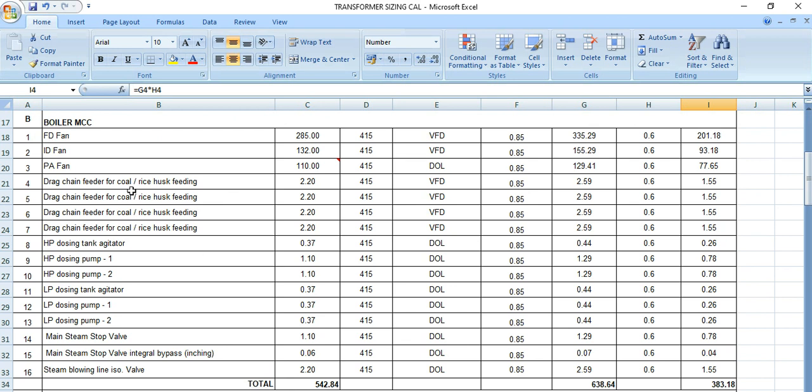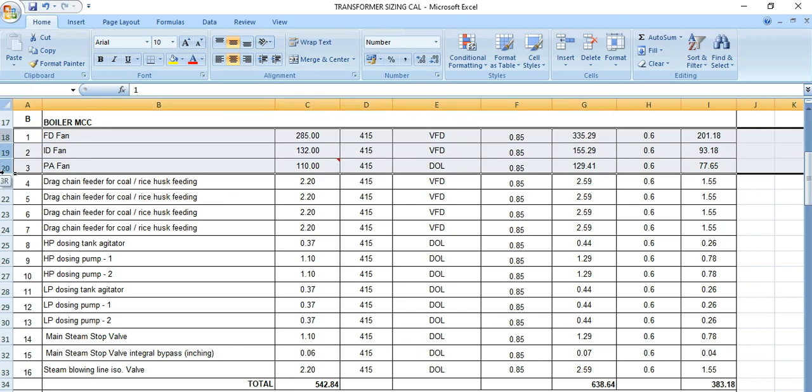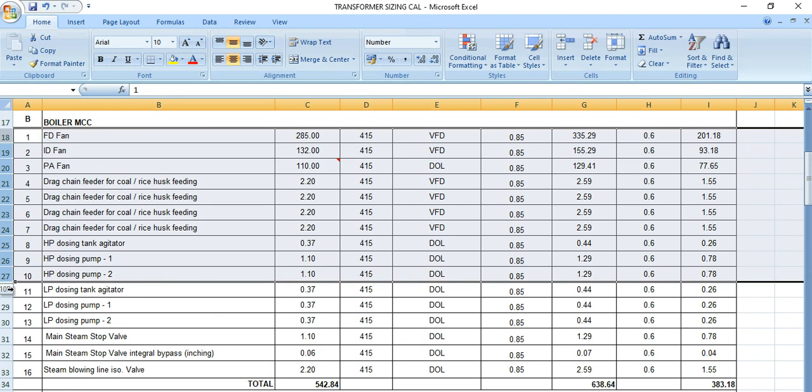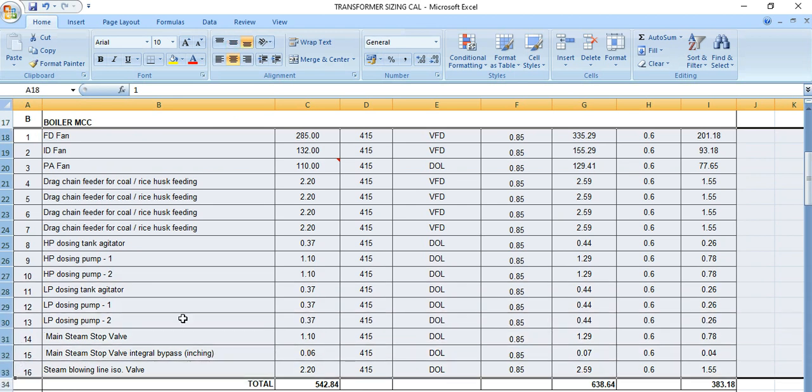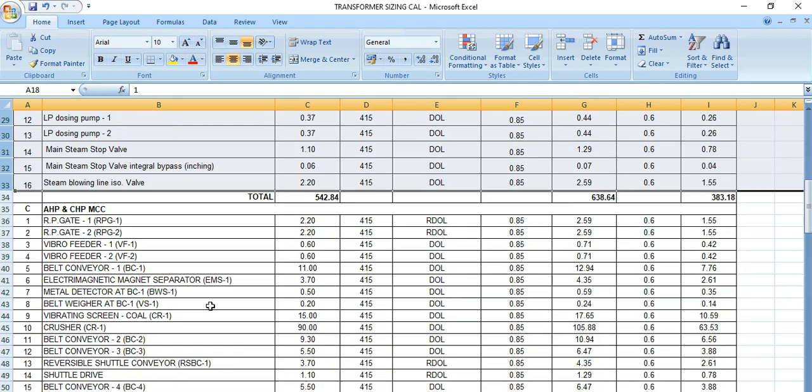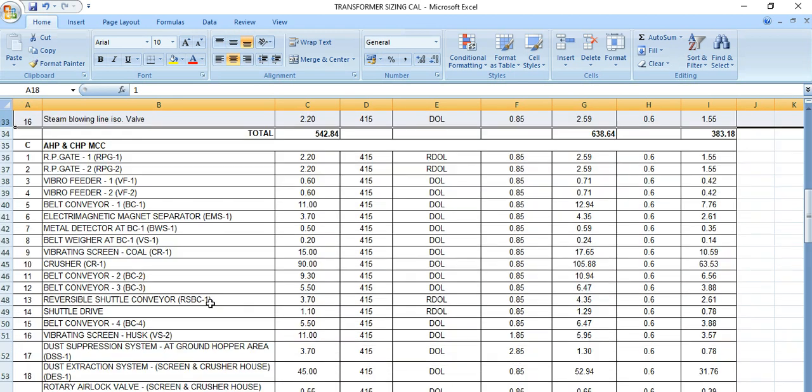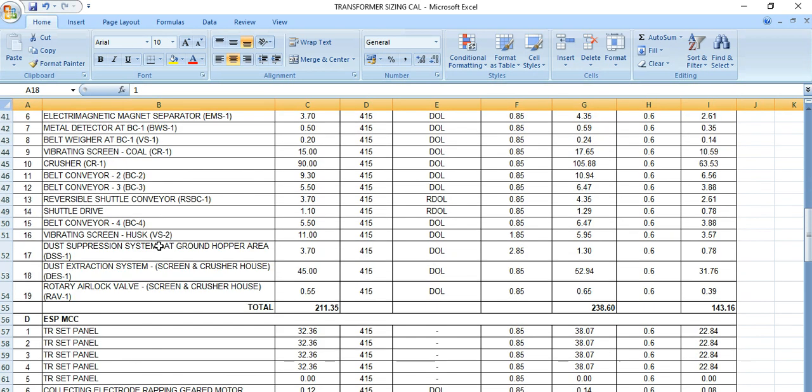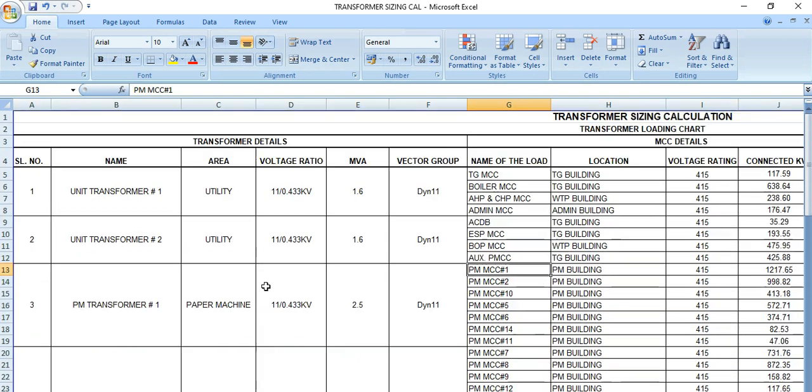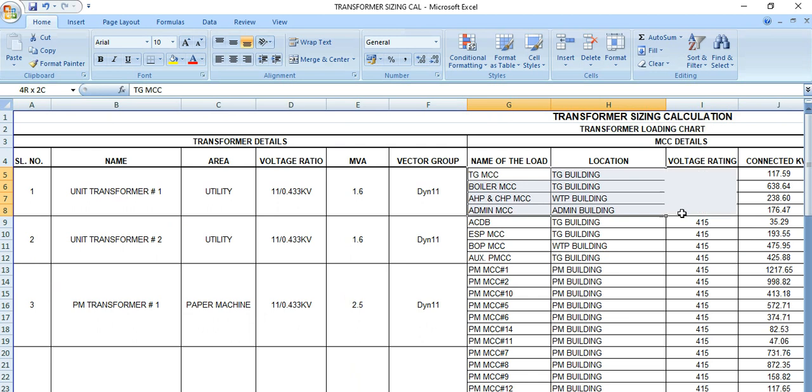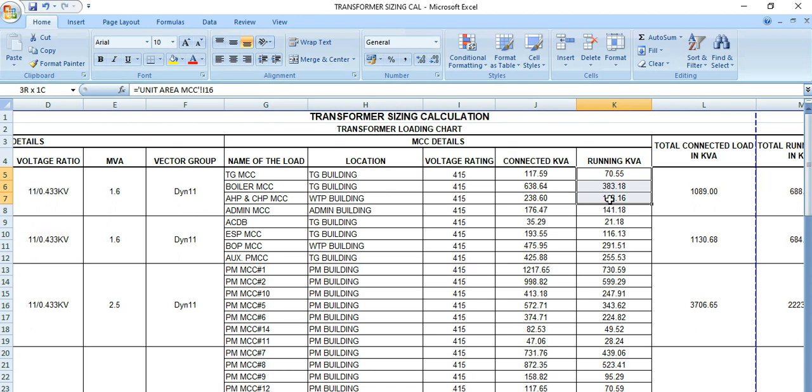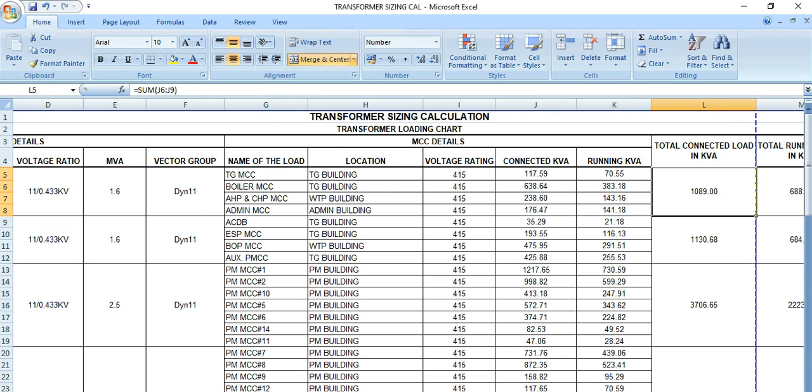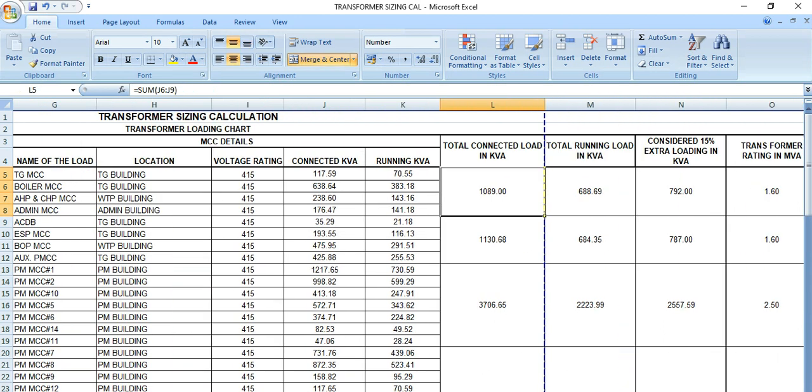So we need to take the help from the load list to find out what are the loads MCC-wise, and then we need to sum up all the loads connected with the individual MCCs. So this is connected kVA, this is running kVA.